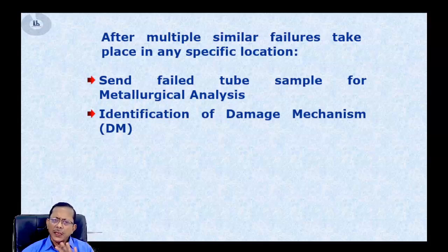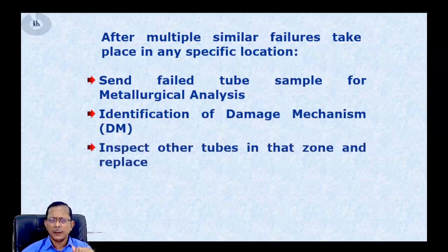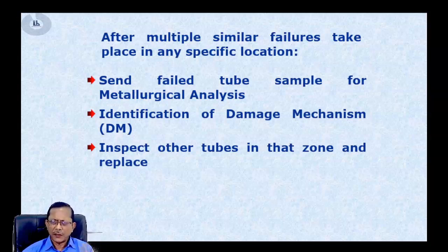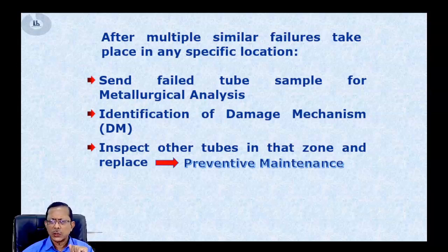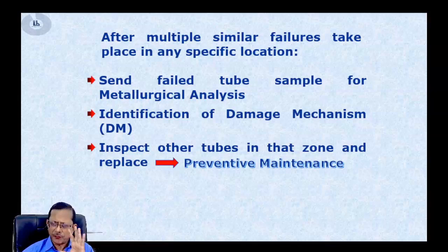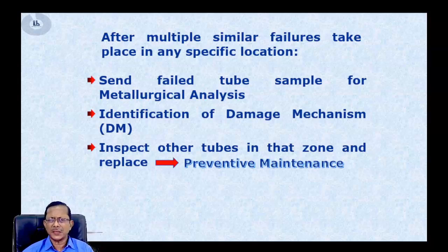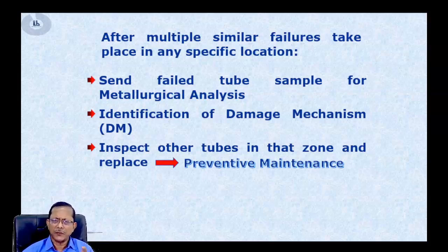Once we understand — say, it's overheating — we inspect the nearby zone tubes to see if similar damage mechanisms are present, and if so, we replace those tubes so they don't fail in the near future. We call this a preventive maintenance practice. But does it prevent a tube failure? Have we removed the root cause — the one mistake actually leading to this damage mechanism? In 90% of cases, no.